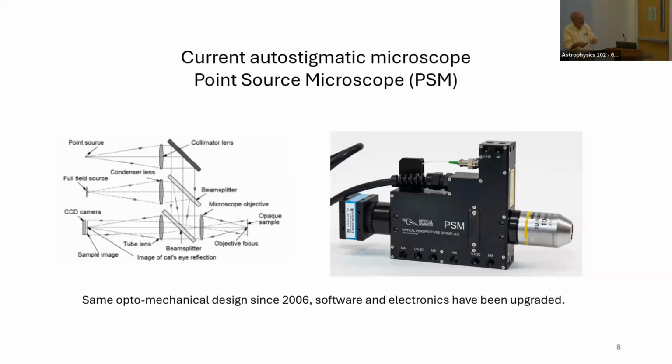And the beauty is, we have a laser diode inside that's fiber coupled into here. There's a storage place here. So if you want to bring in a different wavelength or different power laser, it's just fiber coupled. You need an angle polished patch cord, so the connector has to be angle polished instead of plain polish, but otherwise you can change wavelength or whatever.